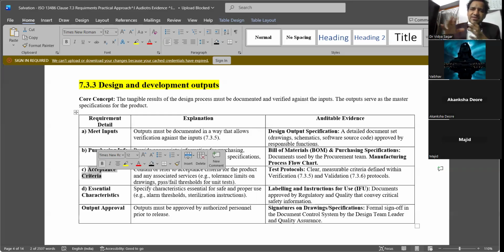So mostly in the first device, you may not get it, but subsequently, as you keep understanding the product material, the prototypes and the designs, and as you keep changing the designs, at some point I'm pretty sure you will come very close. You may not match exactly. It's not like decimal to decimal. It will be somewhere similar, matching your inputs, but still it is fine. Importantly, if the design output is within the tolerances or standard deviation of the input you have provided, it's good. But still you can refine it further.